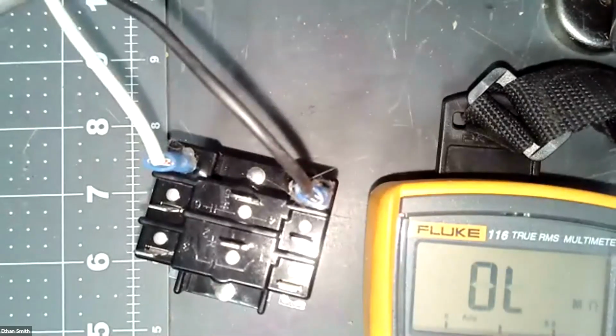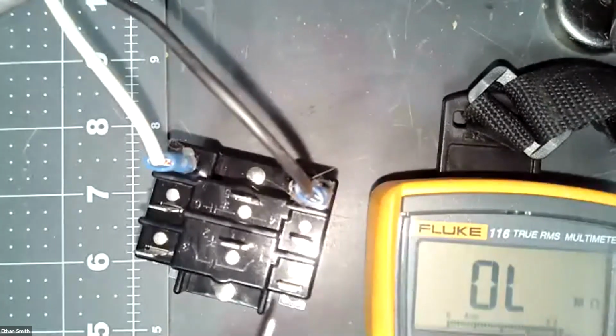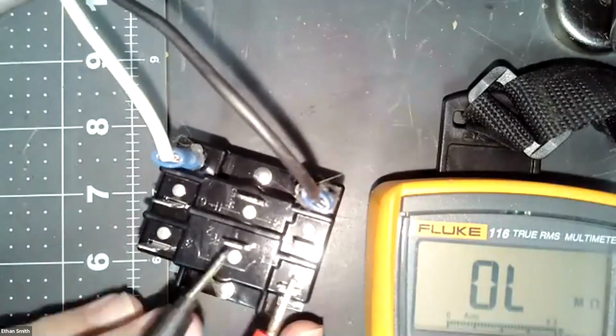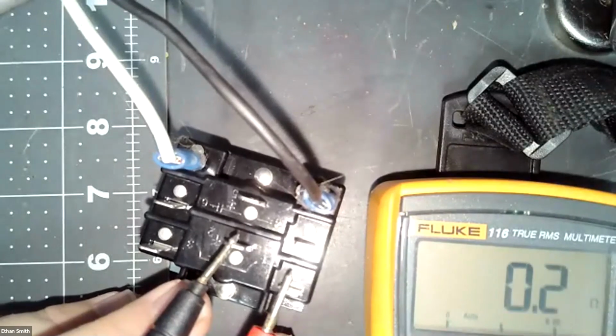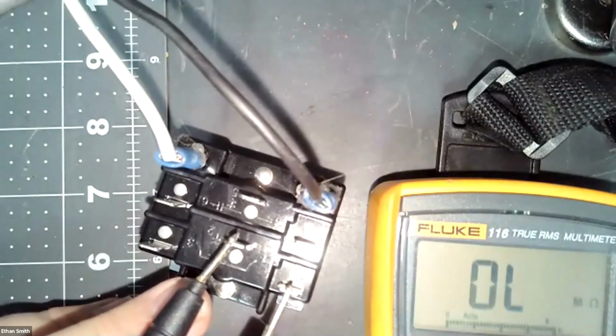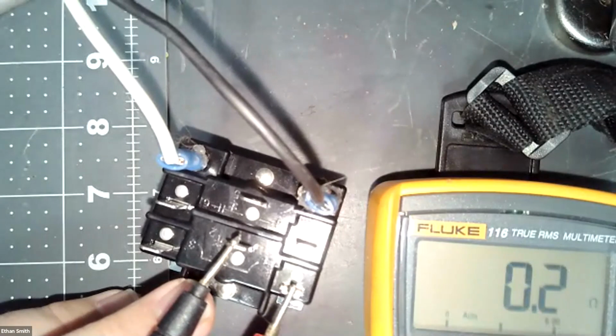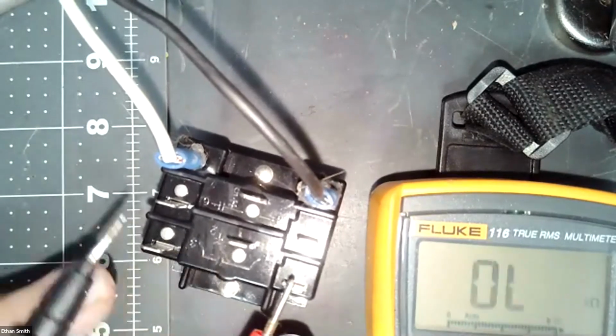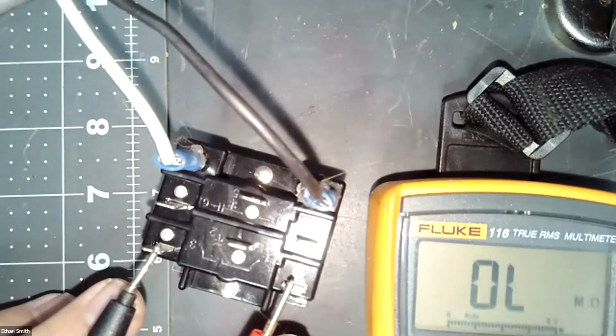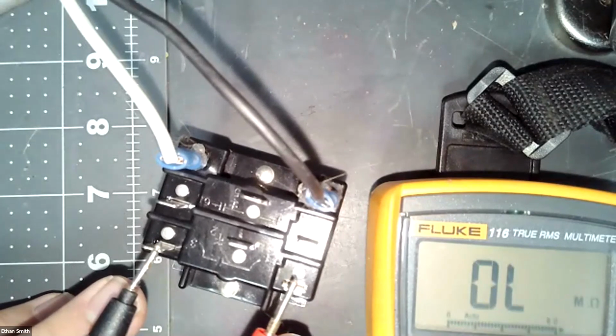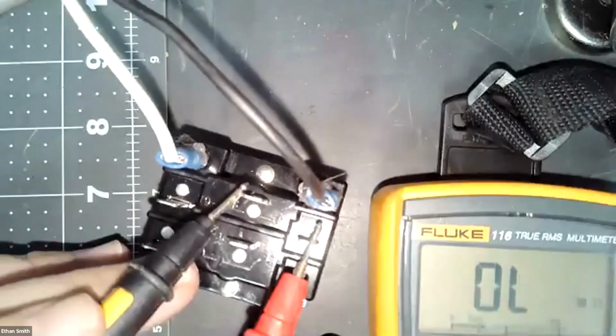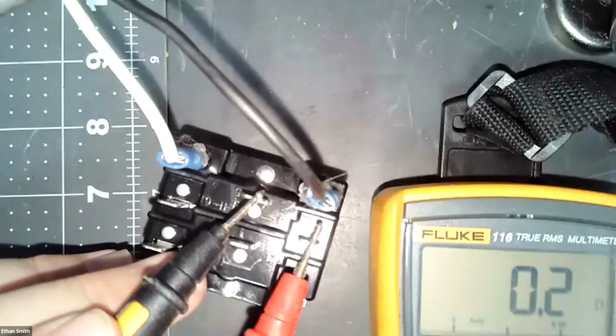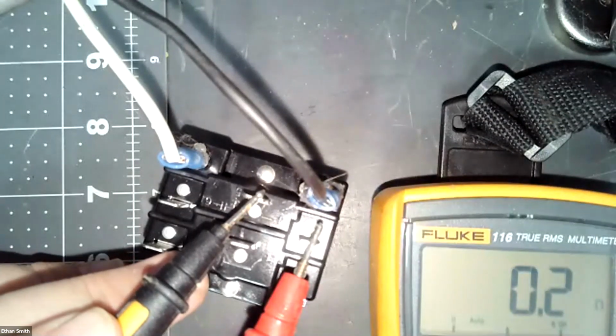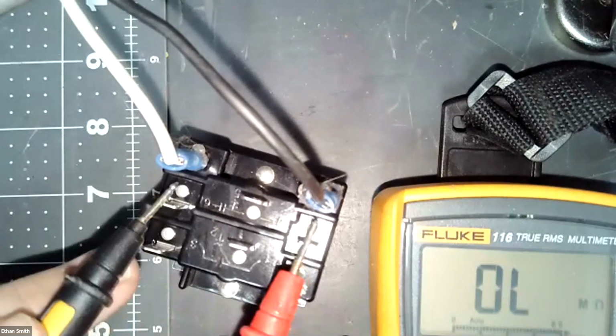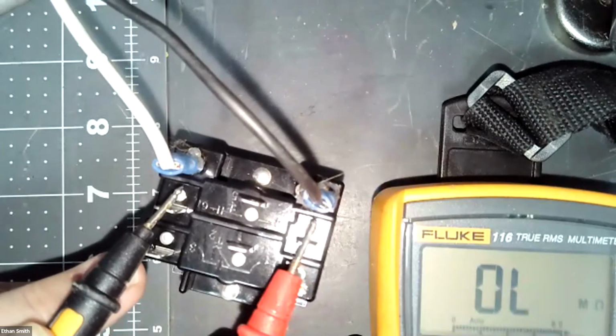I've got it set to read resistance. So if I go to my common terminal, I should have 0 ohms right there. So yep, 0.2, that's almost nothing. That's my normally closed switch. And over here, I should have infinite or OL. So we can see that. Same thing here, infinite, or excuse me, this one's the normally closed, so that's no resistance, and OL on this one, which is infinite. Okay.